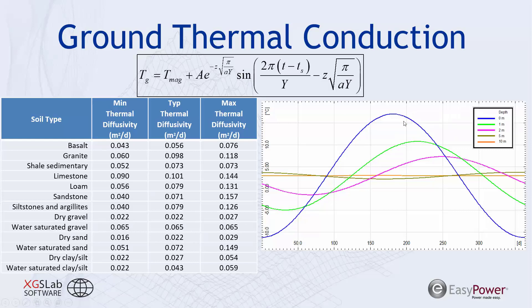The graph on the right: the blue line tracks the air temperature plot — coldest in winter, peaking in mid-summer. Going about a meter deeper, the green line shows the amplitude is attenuated relative to the mean annual ground temperature, and we also see a phase shift. This trend continues as we go deeper into the soil, similar to what you see with large bodies of water — it takes time for thermal energy to transmit into the soil.